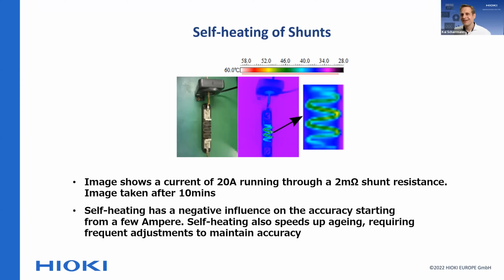Now, if you say that's not a problem, shunts are still very precise at higher temperatures, especially when you consider manganin shunts, which is the typical material used nowadays for shunts. Yes, that's true. Manganin shunts have a very good temperature behavior, or accuracy with regard to temperature. The only problem is that this is only for the shunt material itself. It's not for the connectors that also heat up. It's not for the copper wiring around it that heats up. And that's the part that then causes the inaccuracies in your measurement.